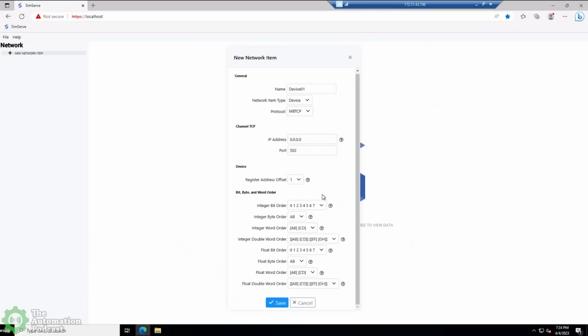That's very important. I know there are different experiences using Modbus with different Allen Bradley products -- some were base 0, some were base 1, so that offset is extremely important. Yes, and if you're working with a SCADA system that doesn't want to change one way, and a PLC that doesn't want to change the other way, you end up jumping through a lot of hoops, right?